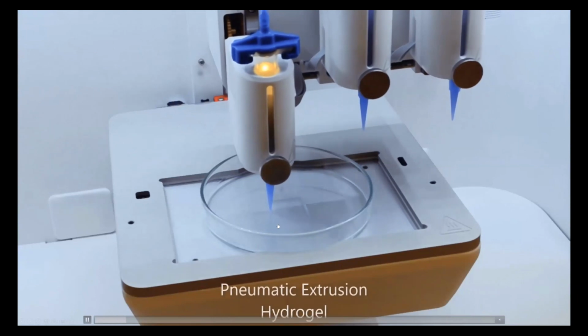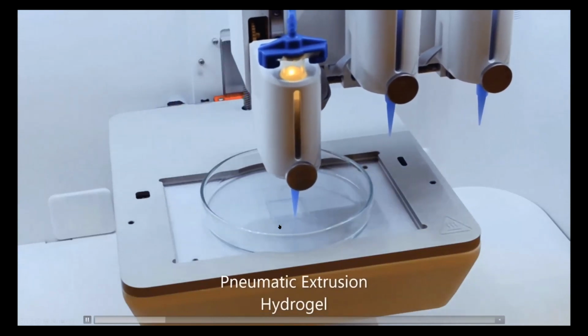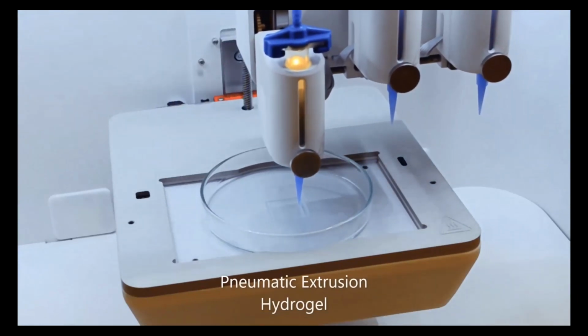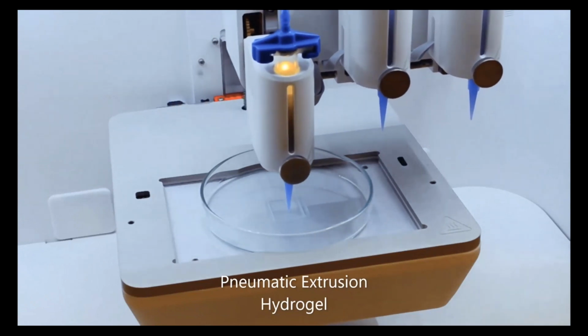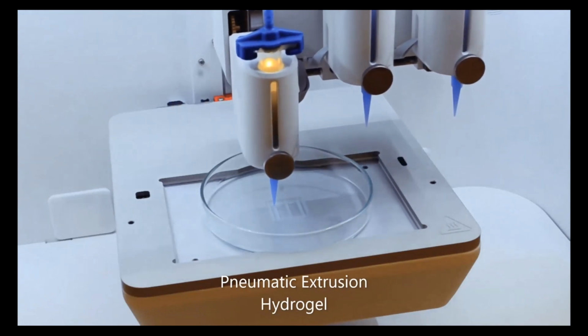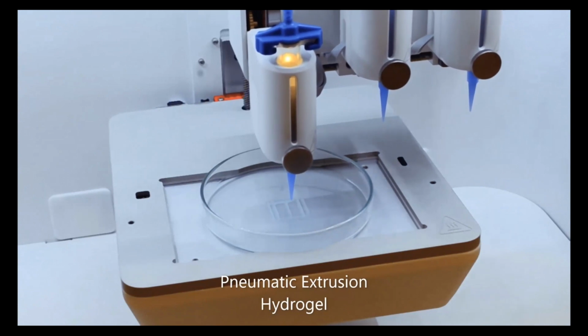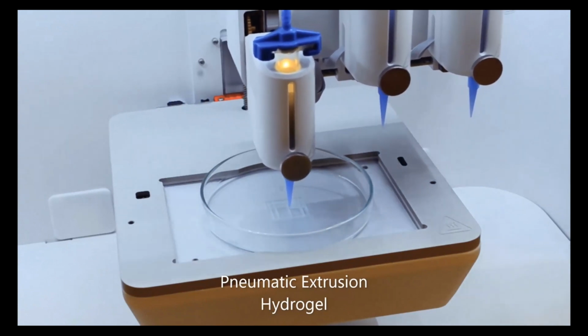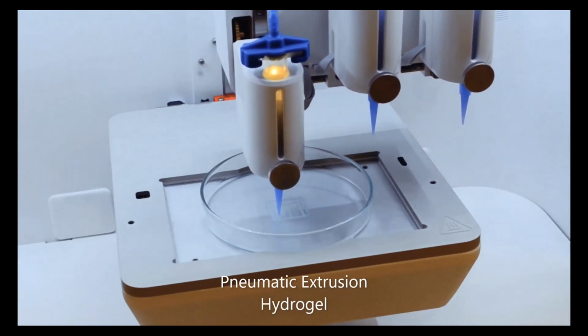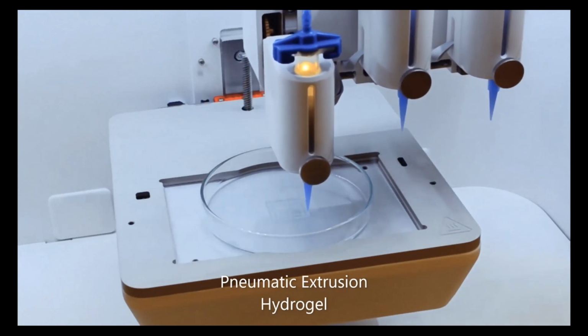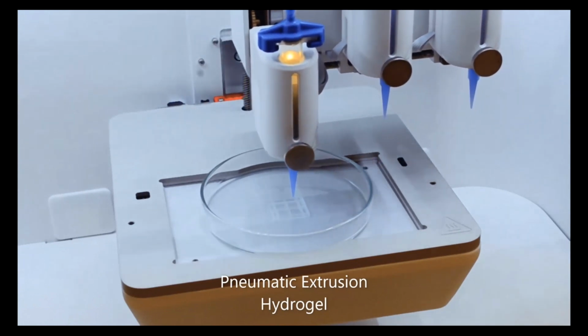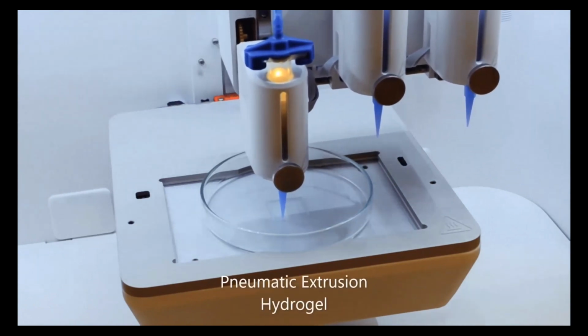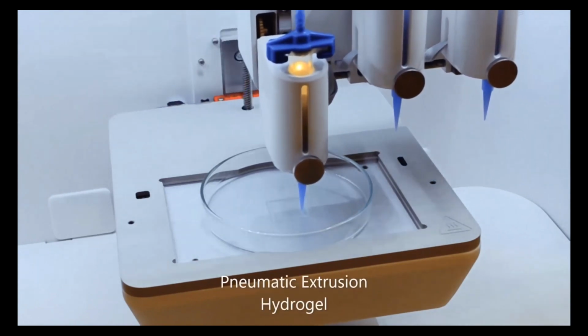Starting with the BioX, it's an extrusion printer, which applies air pressure to a cartridge full of gel, liquid, or melted plastic that is pushed through the nozzle, seen in blue, into a strand. And then stacking these strands layer by layer will result in your printed construct. The simplicity of this approach makes it compatible with a wide variety of biomaterials and solidification types.